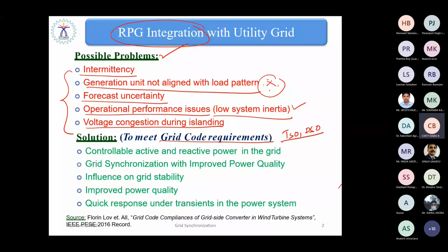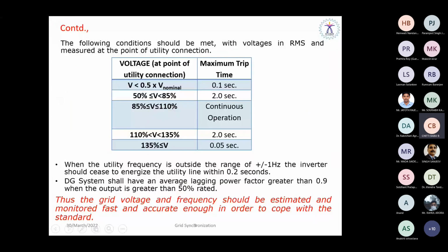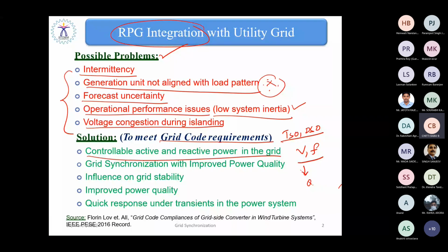Also, we have grid code requirements for solar photovoltaic systems as well. Those requirements include controllable active and reactive power. The grid needs controllable or regulated active and reactive power, as it needs to maintain the grid voltage and frequency constant. As all of us know, the voltage profile at the point of common coupling must be essentially constant, and the frequency profile must be constant irrespective of the grid situation. So ultimately, the voltage profile can be maintained constant by injecting the necessary reactive power Q, and the frequency can be regulated by maintaining the active power balance. That is called active power regulation.